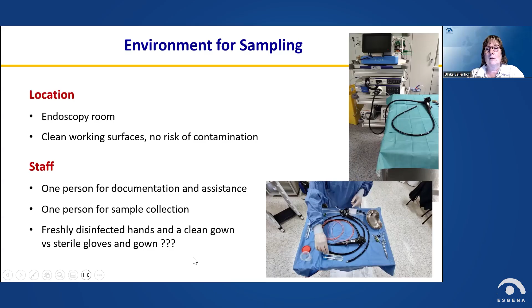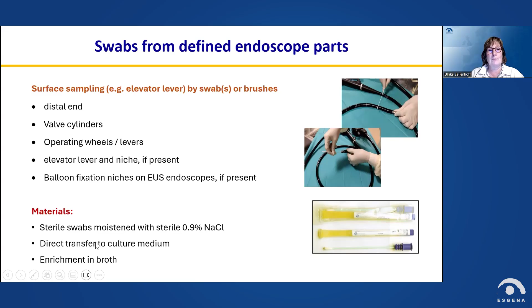With the sampling, we usually start with the swabbing, and you have to identify the critical parts of your endoscope, and this has to be identified per type of endoscope. So I can sample the distal end, and if I have an elevator mechanism, I definitely go behind the elevator niche. I can also have a look at the wheels, at the different valve cylinders, and with EUS scopes, I also go into this niche of the balloon fixation. And I do that with a sterile swab, and then I put that into a transport medium.